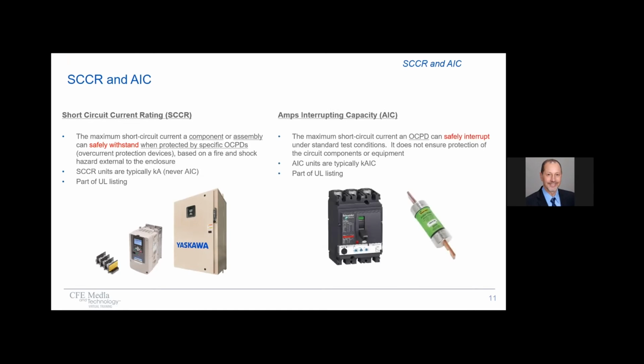Now let's talk about amps interrupting capacity, AIC. Amps interrupting capacity is really the maximum short circuit current that a protective device can safely interrupt. Okay, so we're talking about devices like fuses and breakers, overcurrent protective devices. Okay, and that's the key word there, because on the right-hand side, you can see these devices are capable of interrupting. On the left-hand side, those devices are only capable of withstanding.